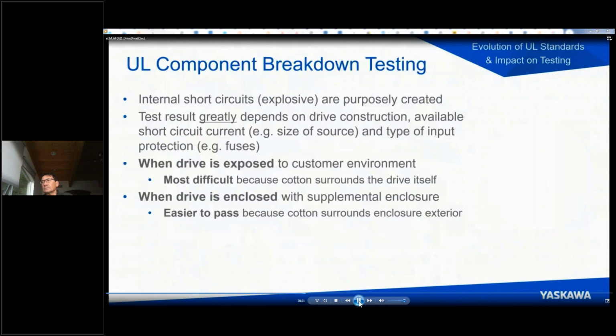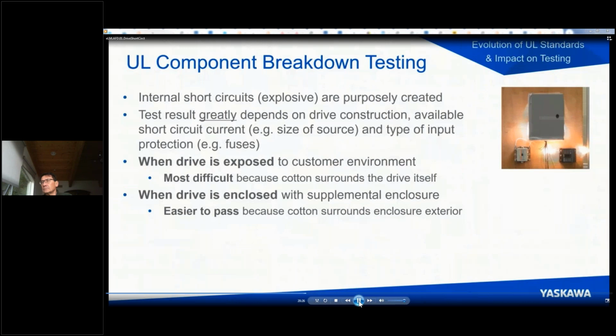Okay, so let's talk a little bit about this component breakdown testing. As I mentioned before, we purposely cause shorts on the internals of the drive and see what happens. With different kinds of devices, whether it be breakers, conventional fusing, or semiconductor fusing on the input, and we see what happens. So the test result greatly depends on the actual construction of the drive, the available fault current, and the type of input protection, as I mentioned. So when a drive is exposed to a customer environment, this is most difficult because we wrap the product or the enclosure with cotton, and essentially the pass-fail criteria, which I'm going to talk about in a little bit, is that the cotton cannot ignite.